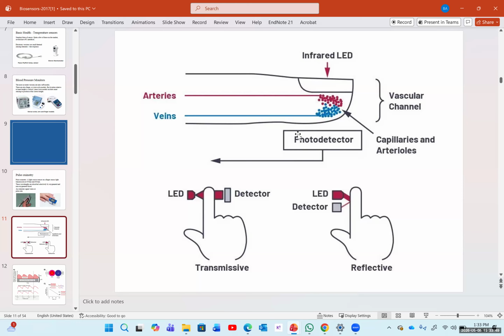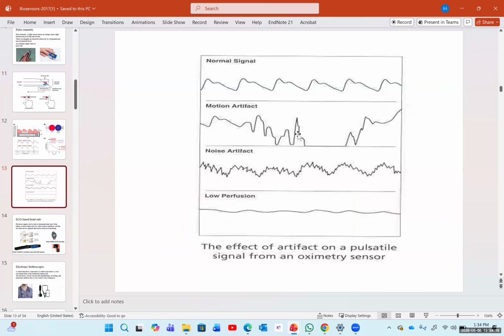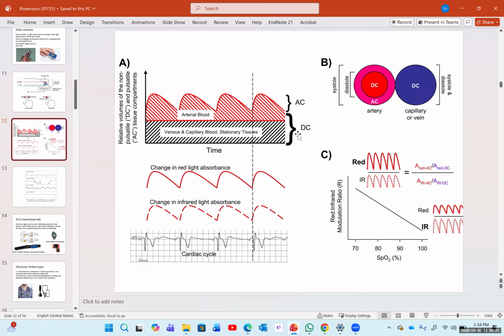So the one on the left is more accurate, and the way it works, oxygenated and deoxygenated blood have slightly different colors. If you look on your vein, you can see the red ones and the dark blue ones. So that means they would absorb different types of light wavelengths. And by reflecting a certain type and measuring the reflection, we can determine the pulse. And the pulse looks something like this. And this is a PPG pulse oximeter, or what we call a photoplethysmogram.